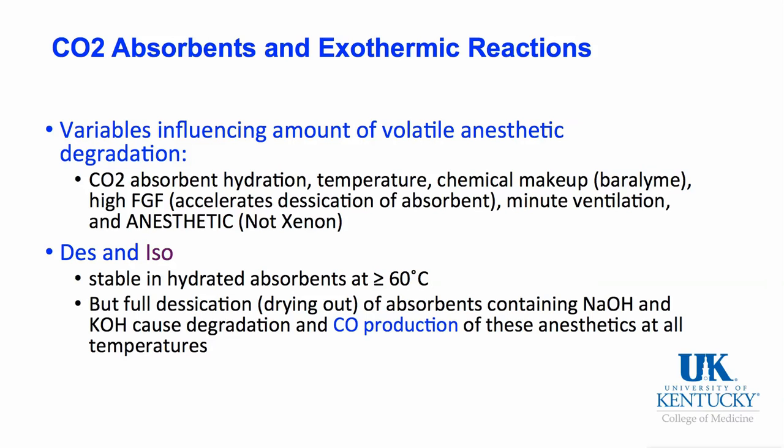Don't try to hydrate it. DES and ISO, as we mentioned earlier, in the presence of these CO2 absorbers, which are very alkaline and hot, can produce carbon monoxide.